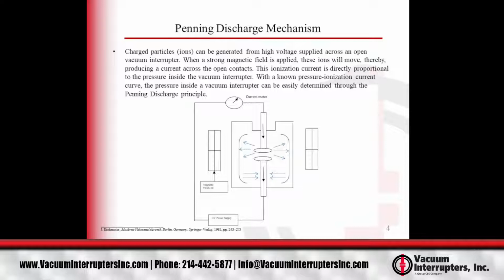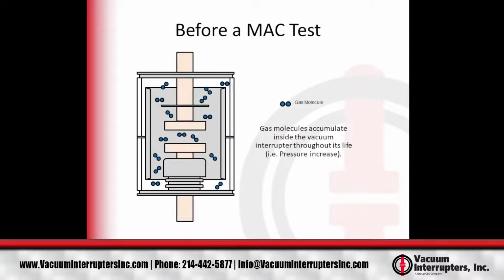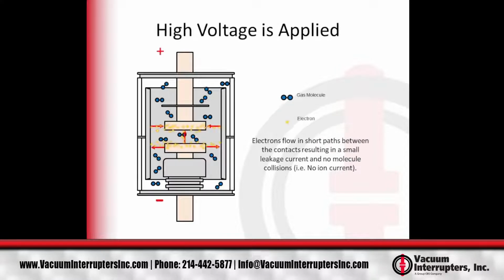We've got a series of curves programmed into the MAC test set, which relate current and pressure. We found that different diameter vacuum interrupters have slightly different curves. So we have 6 generic curves programmed into the MAC test set for the different diameter VIs. Like I said, gas molecules accumulate over the life of the vacuum interrupter. Eventually, enough molecules will have accumulated in the vacuum interrupter that it's unable to insulate the voltage anymore. Go to the next slide, please.